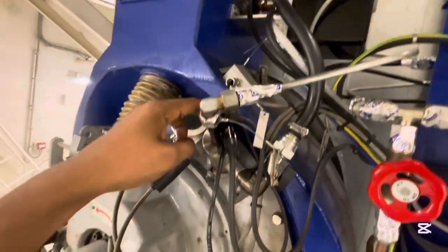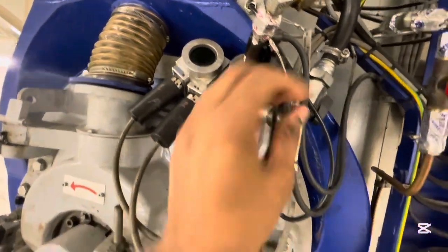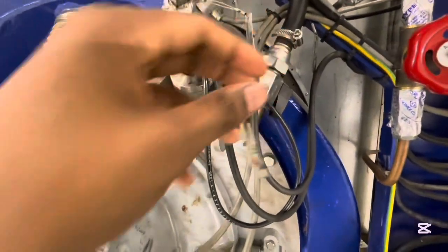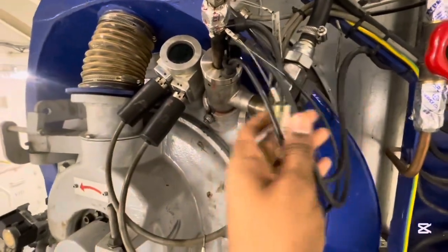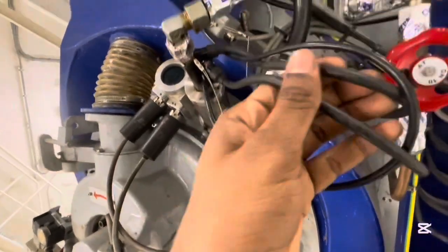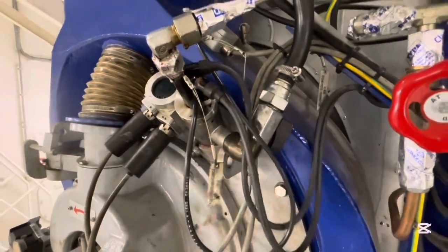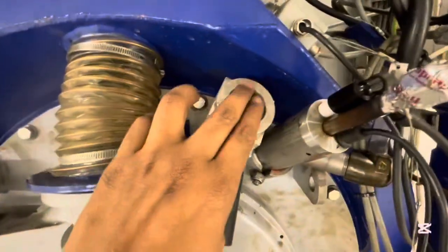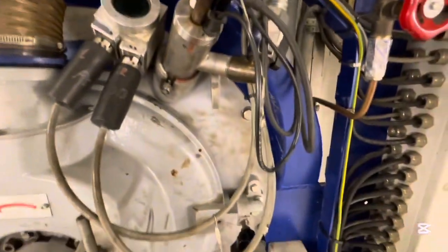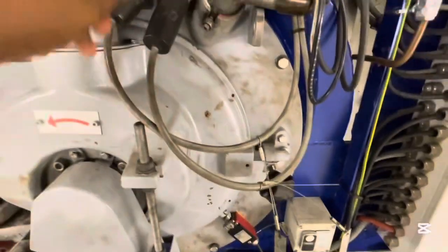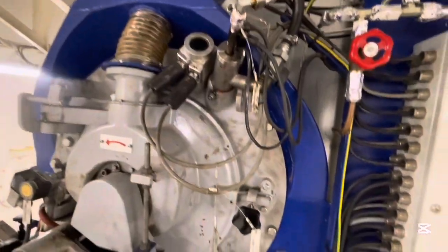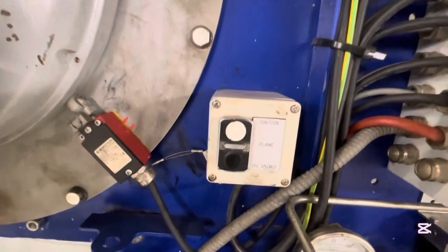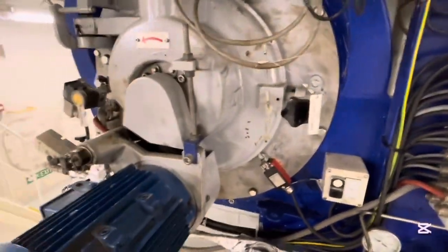This particular unit is called the pilot burner, where the oil is injected, and it is the place where the oil will get ignited using these two black cables from the ignition transformer. The ignition transformer cables are passing the power or current to the electrodes, and once the ignition comes, that is picked up and sensed using a flame eye. So those are the flame eye scanners.